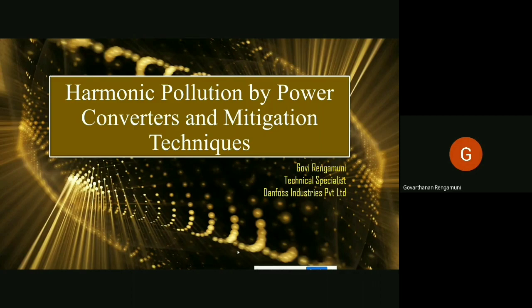It is important to understand the behavior of the input current and input voltage in a power converter before connecting it to the grid, because the current harmonic injection from the power converter is going to be the main reason for the voltage pollution at the grid. So a power electronic or power system engineer who designs a power converter should understand a few things. First, he should understand the grid specification like voltage, current, grid impedance, and pre-distortion that already exists in the grid. Second is the allowable harmonic emission from the power converter he is going to design. The third is thorough analysis of the type of the power converter and what the harmonic limits are. The harmonic limits are always provided by different standard authorities.